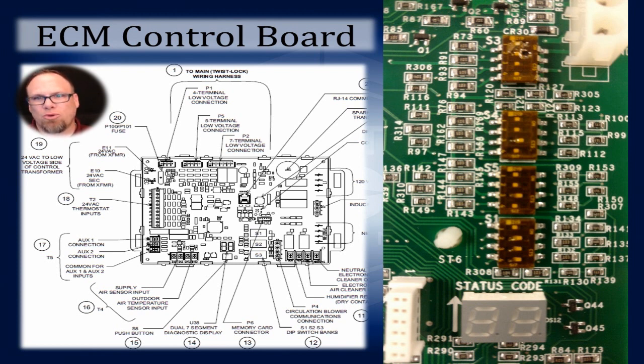As you look at the actual control board that I took a picture of here on the right-hand side, if you look close in the upper left-hand corner of each of those switch banks, they're not in order. The one at the very top, spaced away from the other three, is S3, so switch bank 3. Then after that comes switch bank 4, and then 5, and the one very, very lowest on that totem pole is switch bank 1. Now you can see that those switches on those switch banks go from one position to the other position. One side's on, one side's off, and different configurations of on and off give you different values and programming for how the controls in the rest of that furnace operate, particularly in this case for our variable speed motor.